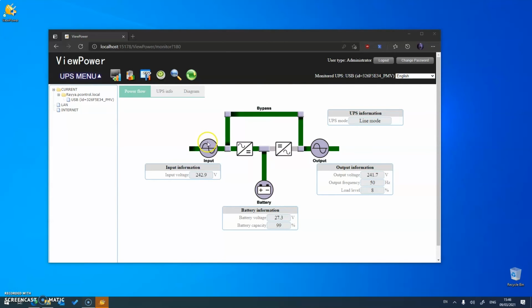Just to summarise, in normal operation, you should be presented with a screen like this. In UPS information, you should have line mode, and there should be no audible beep coming from the UPS. You can see you've got input voltage, output voltage, and the load as well, which has got a little bit of load on right now, just for the purpose of the test.